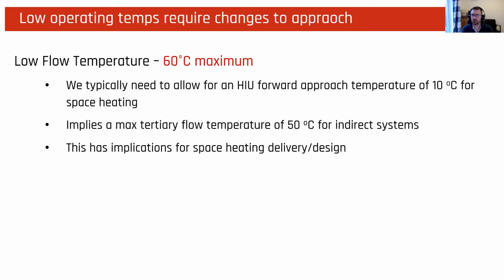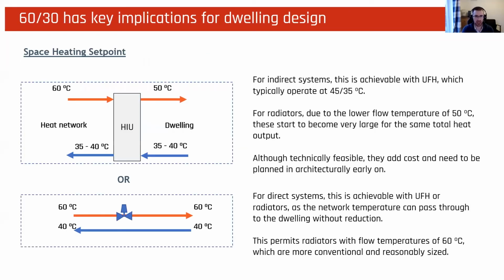That's one of the most common issues we come up against when we're trying to integrate heat pumps on new build developments. Because 50 degrees is quite low temperature compared to conventional tertiary dwelling heating systems. So this diagram is showing 60 degrees coming in from our heat network to the HIU and supplying 50 degrees to our space heating system. Now for underfloor heating, that's not a problem. Most commonly, we would see underfloor heating systems designed at 45 flow temperature, so that can easily be delivered from 60-degree flow temperature on the network.